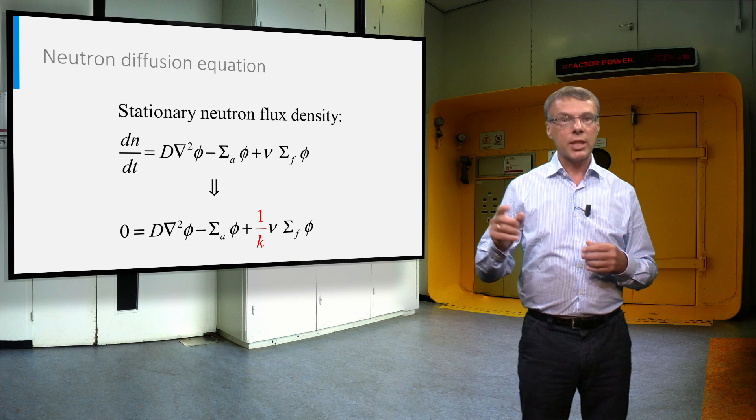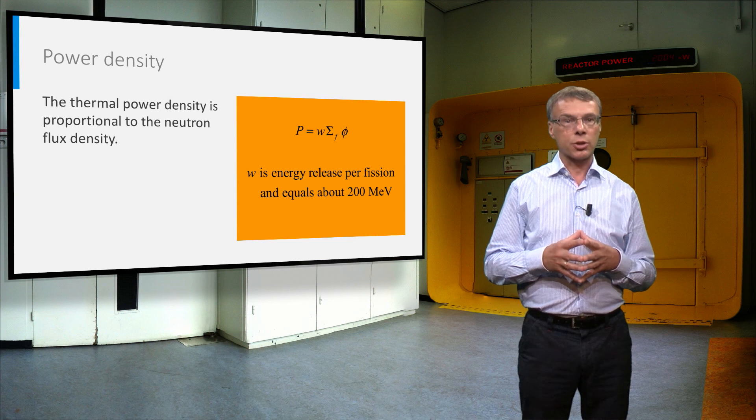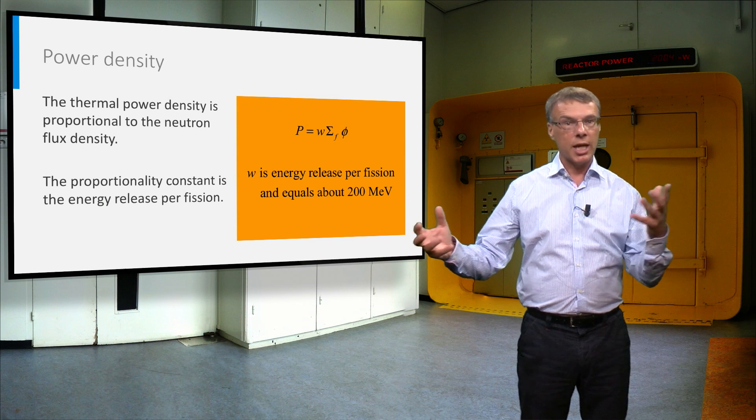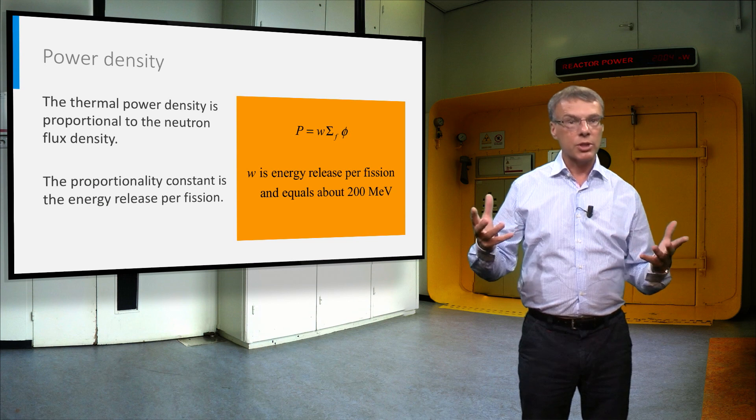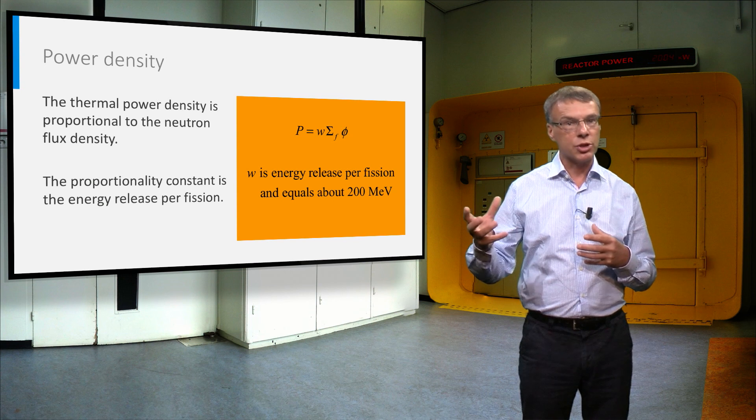From the neutron flux density we can calculate the power density in a reactor core. There is a simple relationship between the neutron flux density and the power density by first calculating the fission reaction rate and multiplying this with the energy release per fission.